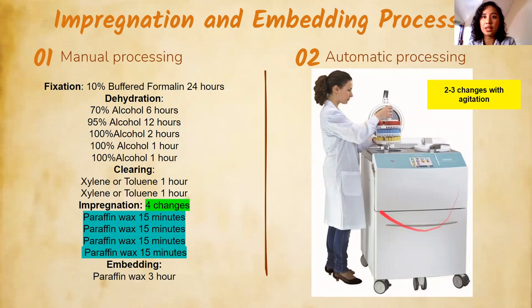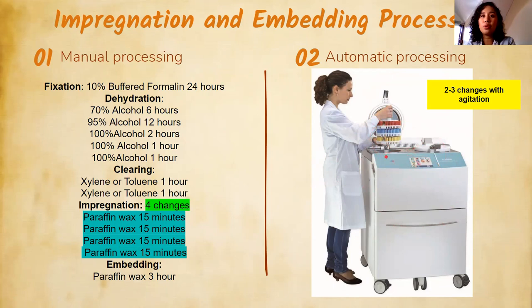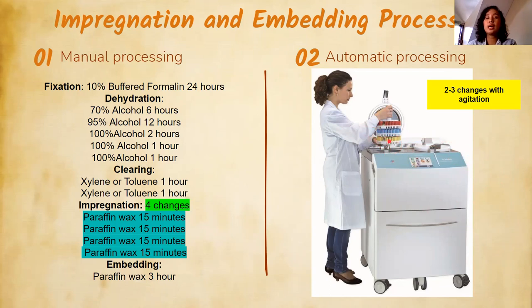For automatic processors like the Logos machine, it is a tissue fluid transfer system where the cassettes don't move. You can process many cassettes at one time. For example, when a large organ like a uterus arrives — with fallopian tubes, uterus, endometrium — the pathologist may want many tissue sections and uses multiple cassettes. With the automatic processor, you can process many cassettes simultaneously.